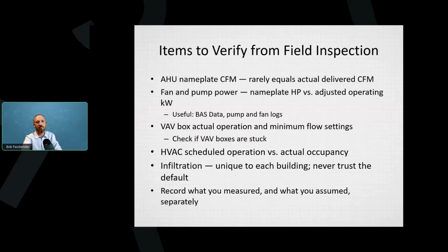Building automation systems are probably one of the best ways to pay back, and that's if you can get the scheduled operation to match the actual occupancy without having overrides destroy your operation. Infiltration is unique to every building. You could have two people build the exact same building, or the same person build the exact same building twice, and it will have different infiltration just based on how it was exactly installed. And so you can never trust the default on infiltration. Bottom line there is you want to record what you measured and what you assumed. And if you can find some assumptions that you weren't aware you used, you would also want to record that.